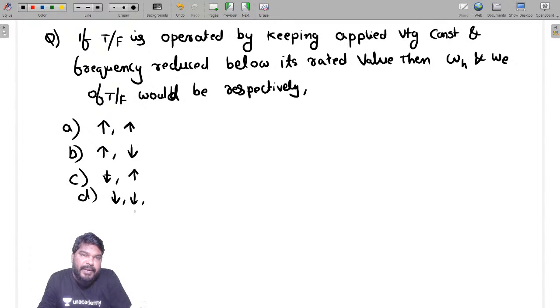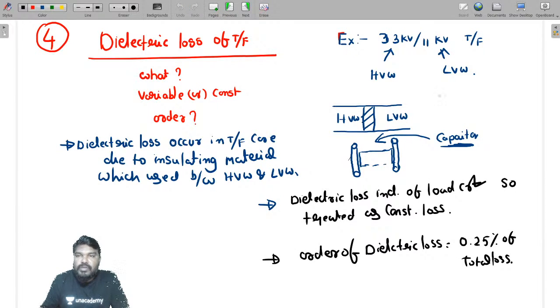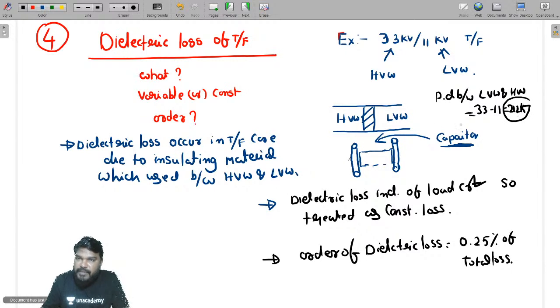Why? Because it depends on the potential difference between the LV winding and HV winding. So that is 33 minus 11, equal to 22 kV. To withstand this 22 kV, we have to provide the insulation. The insulation requirement depends on the applied voltage, but not the load current. That's why it is treated as a constant loss.